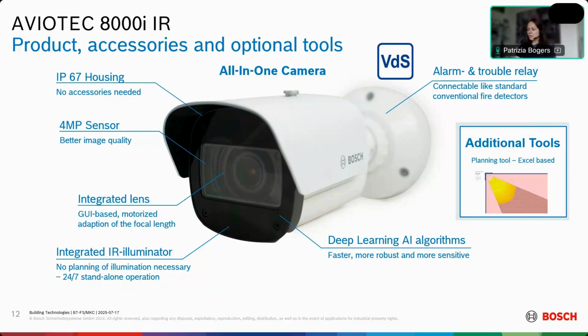Last but not least, and not to forget, since this year we have reached the so-called VDS certification according to VDS regulation 3847 for video-based fire detection. VDS, as Europe's top certifier for fire protection systems, tested the camera with different test fires and it also underwent rigorous environmental tests, be it mechanical, thermal, or electrical.